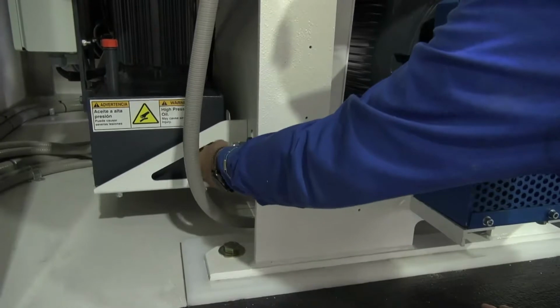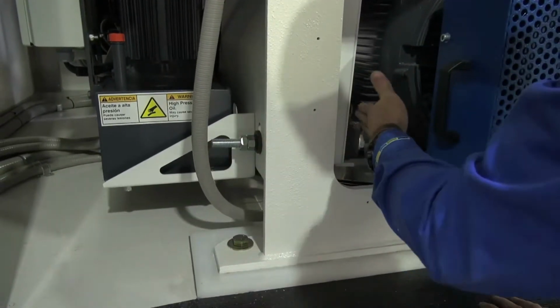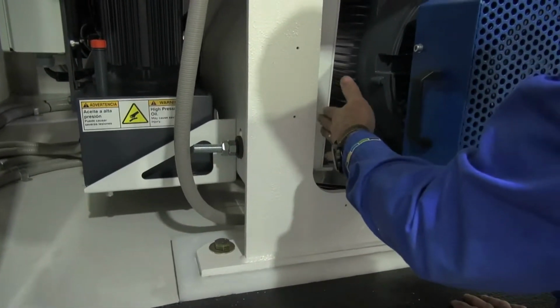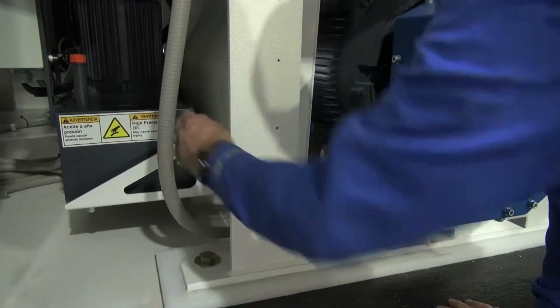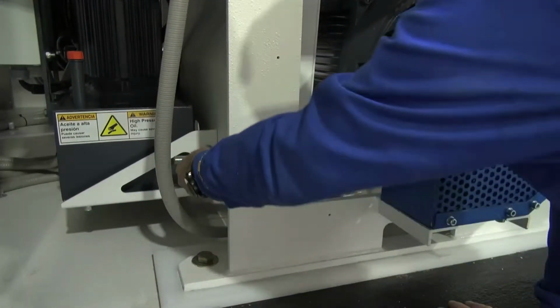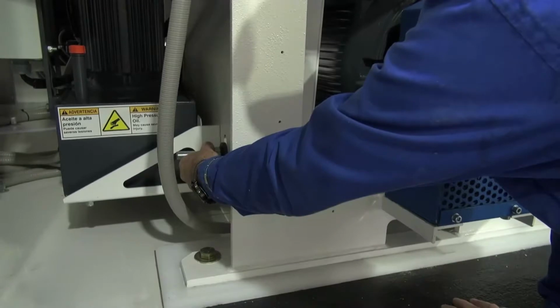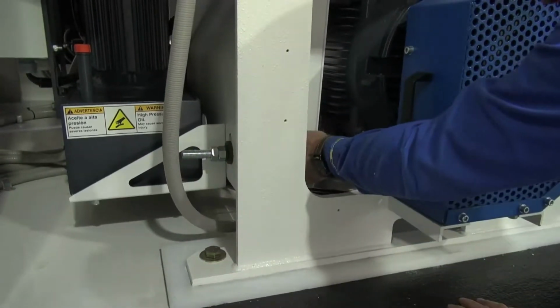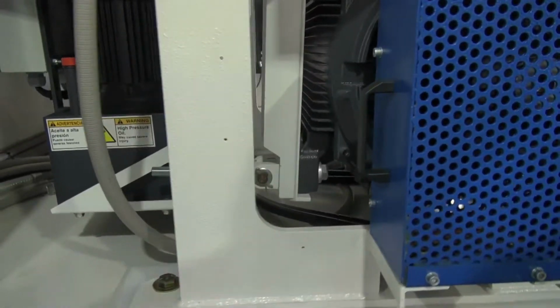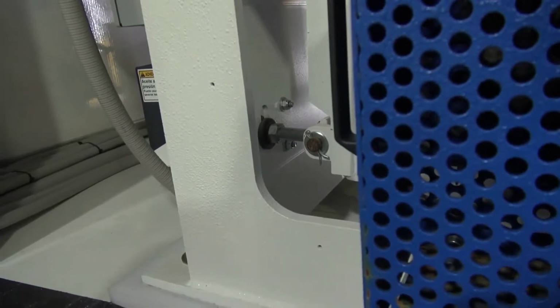It's important when you remove these nuts and adjust this belt tension. We tighten this bolt to adjust the tension. We double nut to jam nut the outside bolt. And then the inside bolt is critical that it is retightened so that it doesn't come loose as we get some bounce from the machine running.